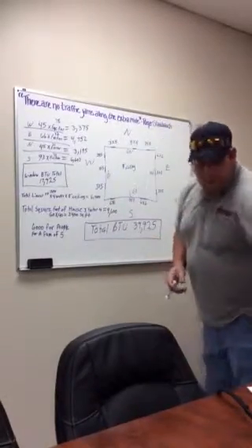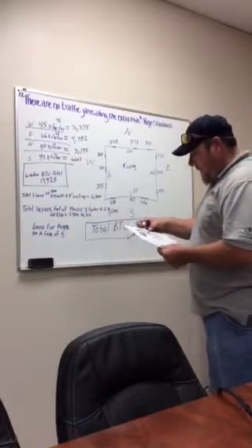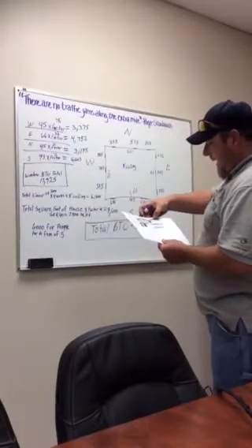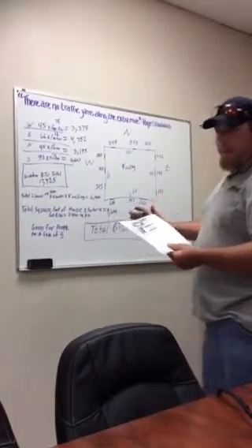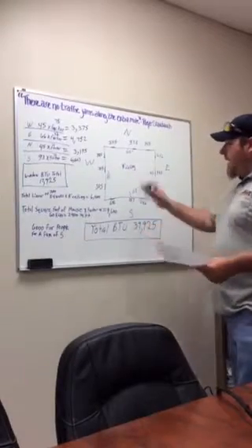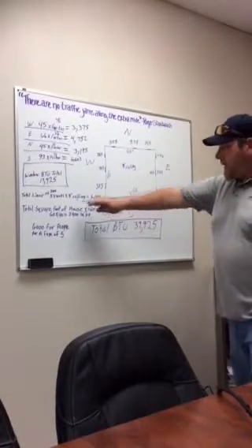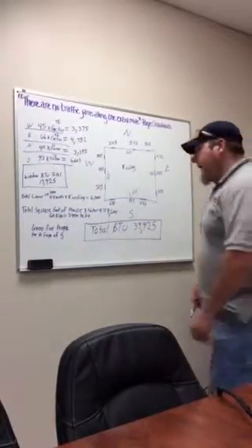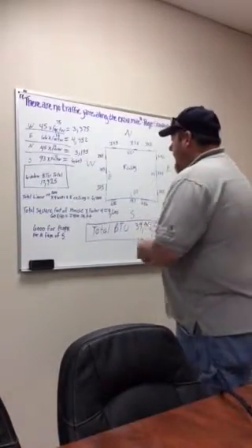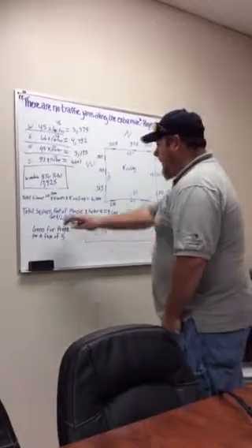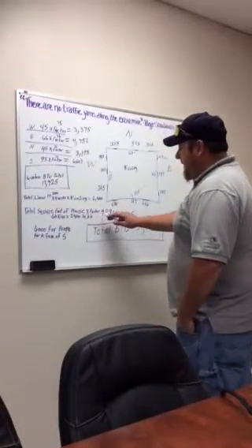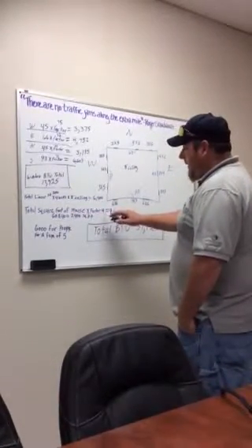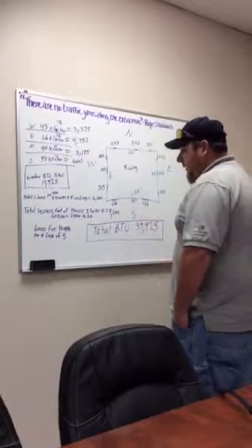So these are why we went with the lower factors. Now there are other factors in your sheet. There's 6.3, there's 8, there's 10 for like no insulation. So it really depends on how much insulation is in the house to determine your factor on your loads. But those factors are all in your sheet. Okay, so then what we did is we totaled all that up, and we times it by 4 because we used a factor of 4, and that came up to 9,600.